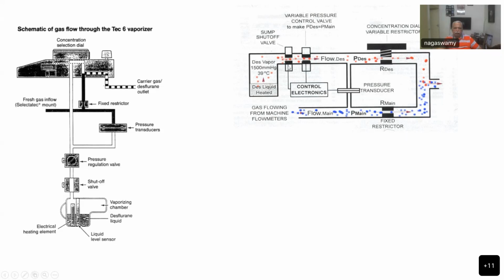There is an immediate shut-off valve outside the sump, as I told earlier, and there is another resistor. So the flow is happening here, and this connecting tube in between has what is called the differential pressure transducer. Depending upon the changes between the pressure in this tube and the pressure in this tube, this transducer uses the control electronics to maintain the same percentage of gas. And this is the dial setting which we operate to set the concentration that we want. This dial setting has an optical sensor which will immediately open up the sump shut-off valve and allow the gases to flow. So that is a very important point.